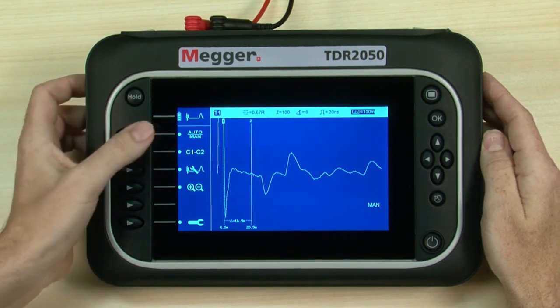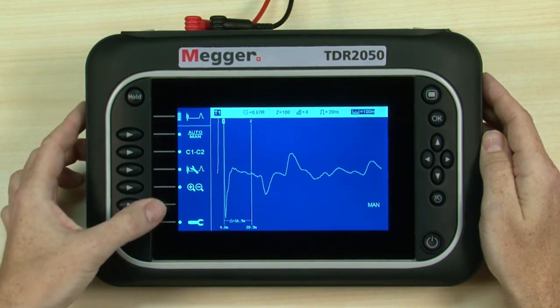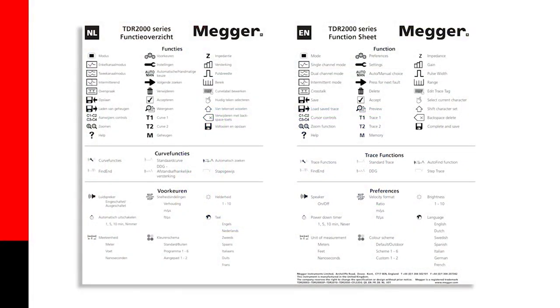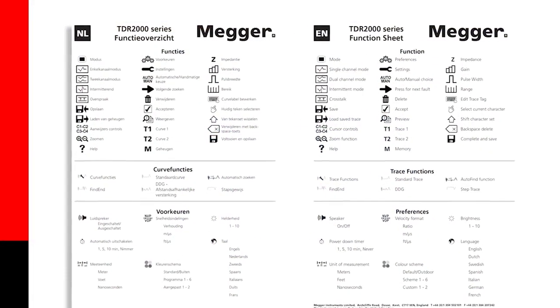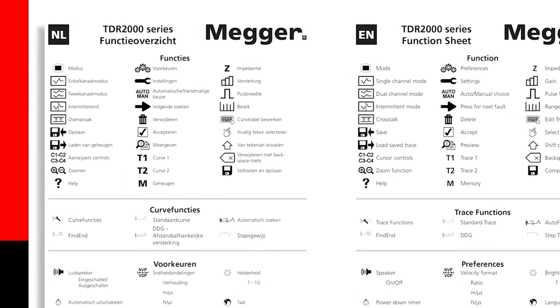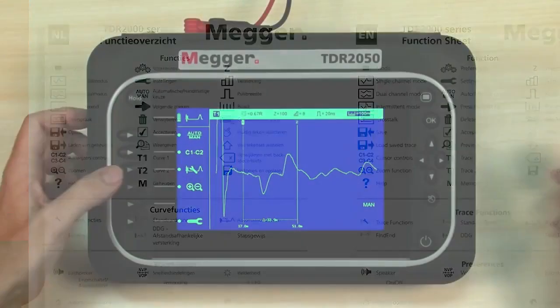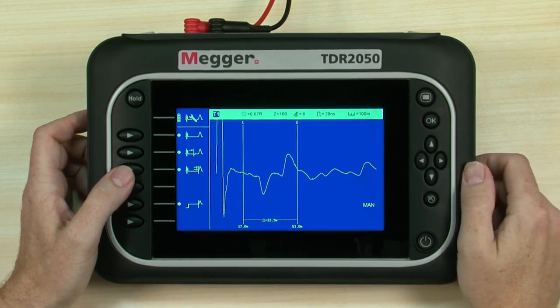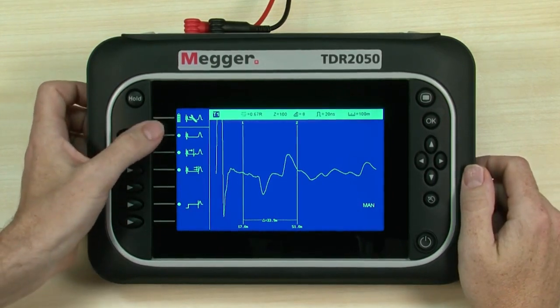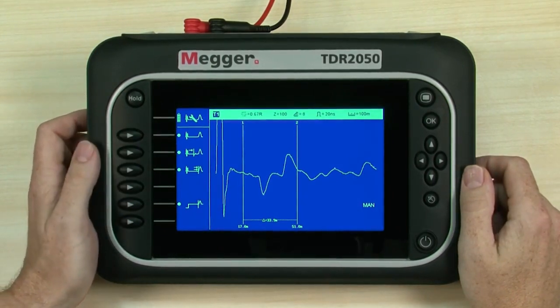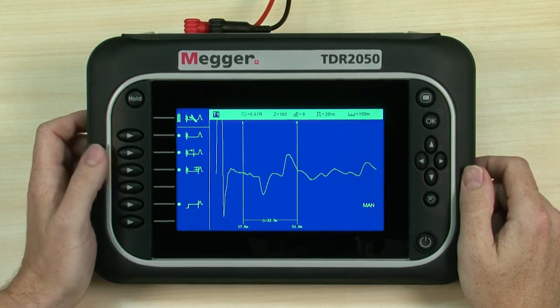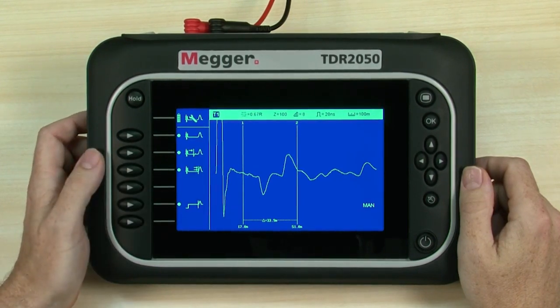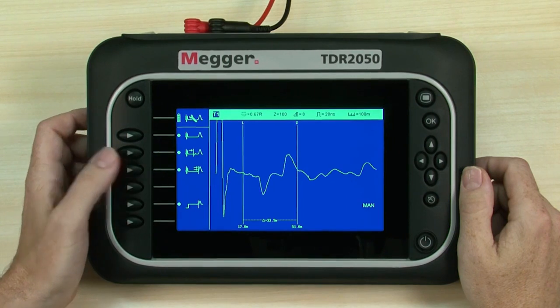Menu icons identify individual functions or groups of functions. For those who like a crib sheet, we supply a full list of icons and functions on the printed function sheet. We need to select the trace functions menu. Here we can see a list of functions available for our chosen settings. Find end automatically determines the end of the cable — useful for fast measurement of cable length.